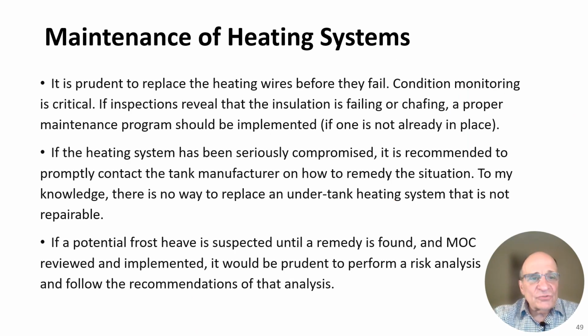Maintenance of the heating system is extremely important. It is prudent to replace the heating wires before they fail. Condition monitoring is critical. If inspections reveal that the insulation is failing or chafing, a proper maintenance program should be implemented if one is not already in place. If the heating system has been seriously compromised, it is recommended to promptly contact the tank manufacturer on how to remedy the situation. To my knowledge, there is no way to replace an under-tank heating system that are not repairable. There are some methods of coming in from both sides with heat tracing, but if, let's say, the conduit is pulled apart, there's no way to replace that conduit.